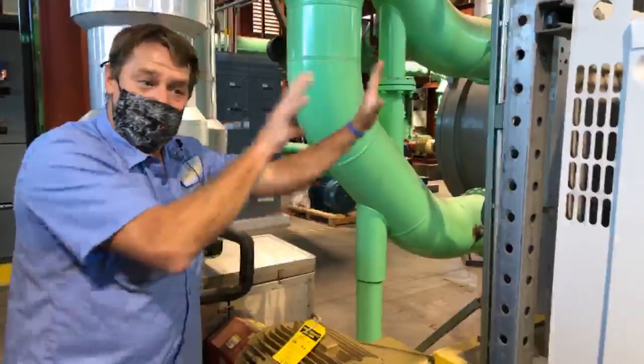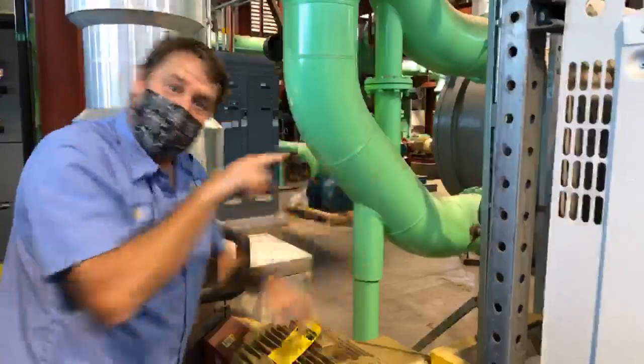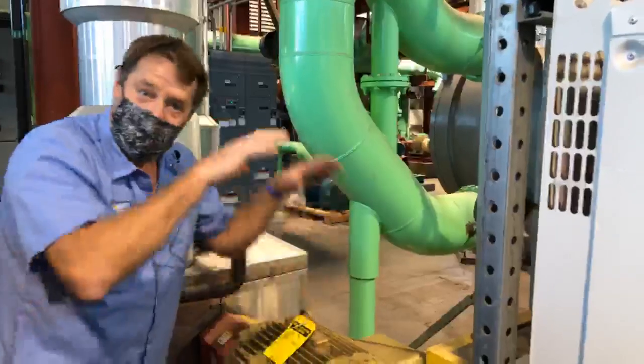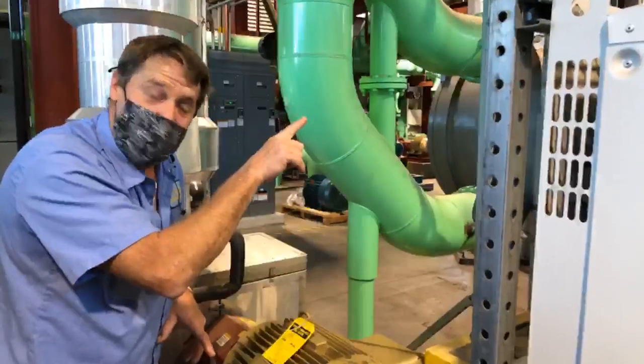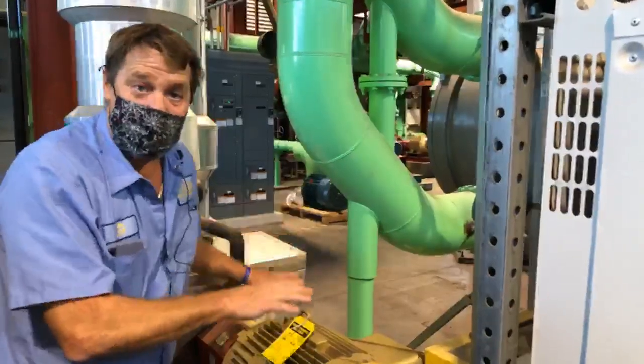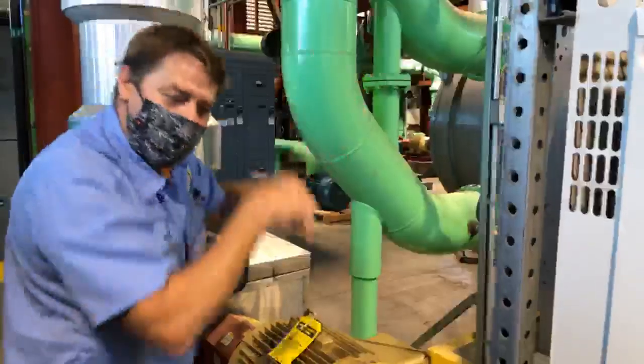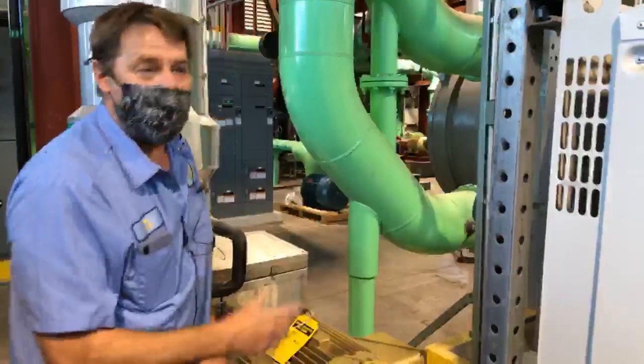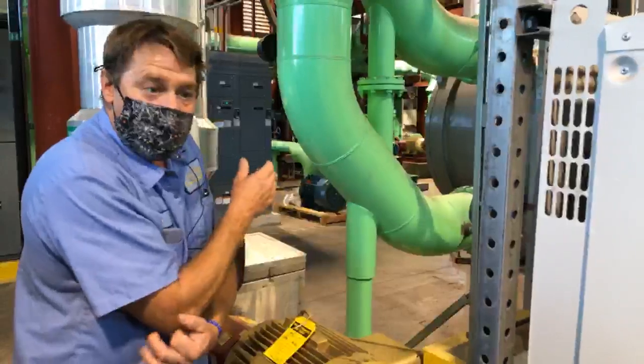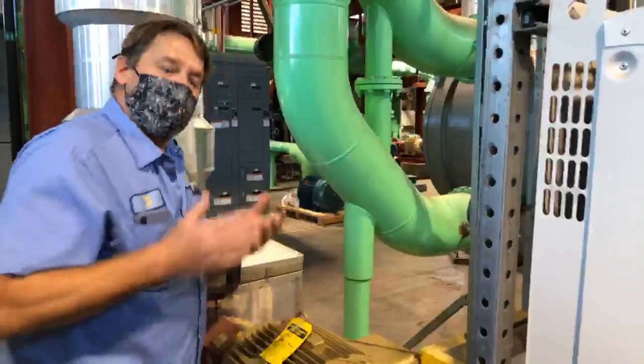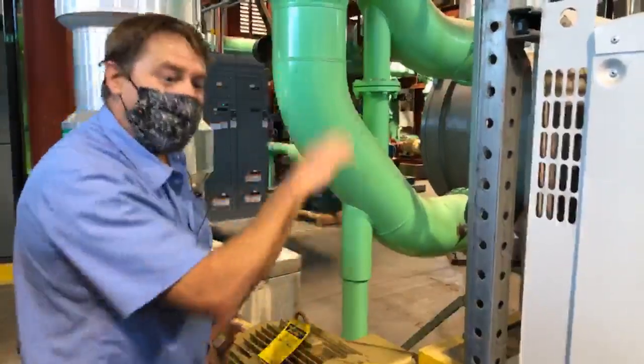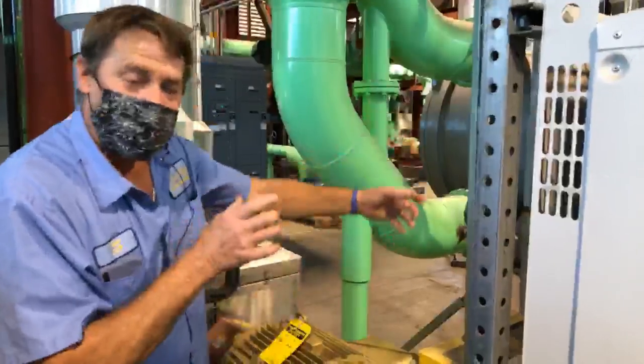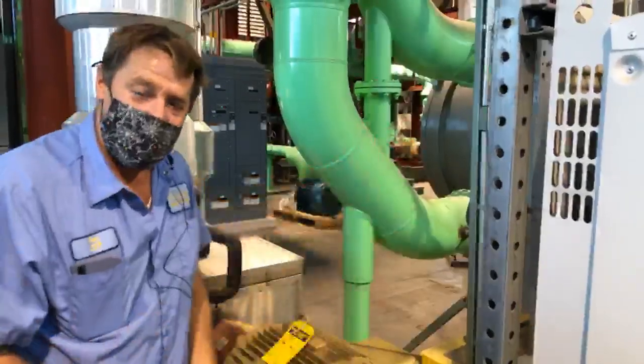Gotcha. And usually, just like over at the central plant and here, the pipe going out and the pipe coming back from the customers, we maintain a delta P across there. So those pumps are variable speed. These pumps are across the line. They're just going. The pumps that go to the customer, in this case, the East Campus medical side, speed up and slow down to keep a differential pressure across the supply and the return header.